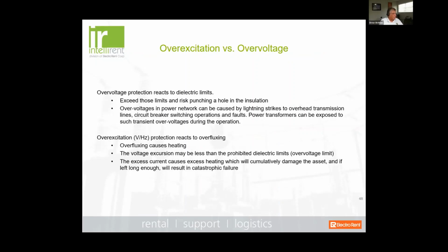Okay, so what's the difference between overexcitation and overvoltage? Well, overvoltage reacts to dielectric limits. So if we exceed those limits, we risk essentially just punching a hole in the insulation. Overvoltages in a power network can be caused by lightning strikes to overhead transmission lines, circuit breaker switching operations and faults. Anything that would subject the transformer to an overvoltage.